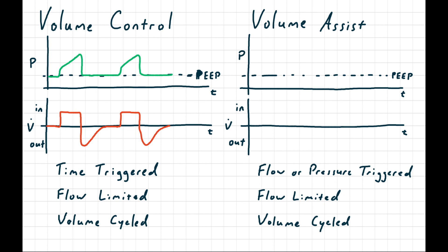The circuit pressure starts at PEEP because we're at end expiration. Flow is zero because the circuit pressure matches the pulmonary pressure. If the patient tries to take a breath themselves, the circuit pressure is going to go down a little bit because the patient is effectively sucking on the endotracheal tube. That will also trigger a little bit of flow into the patient if the inspiratory valve is able to open. The ventilator then recognizes either the drop in pressure or the increase in flow.